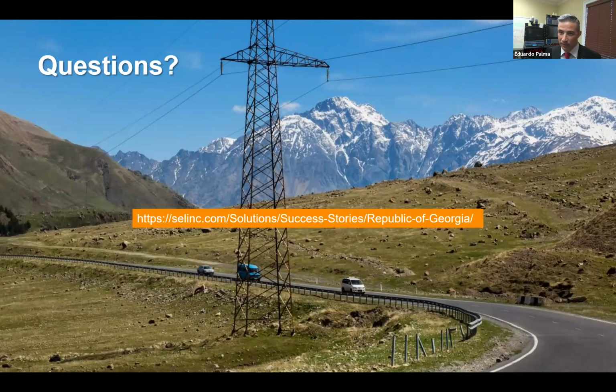technology that is the best technology to implement when you want to see and actually measure into a report that you can then analyze post-mortem, after the event. This technology is called synchrophasors. We mentioned it. With synchrophasors, what you receive is information from a distributed network of PMUs, or phasor measurement units, that allow you to understand whether the damping is a positive value or a negative value in your power system when things happen, like, for example, disconnecting a transmission line, or a generation plant coming onto the system.